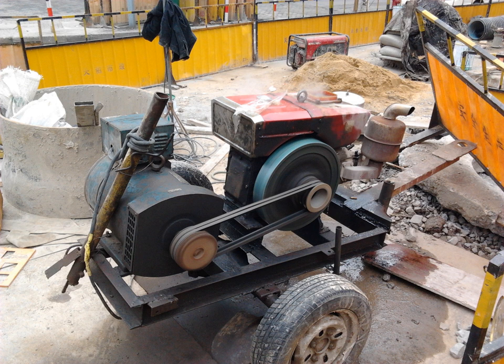This produces power at 50 Hz, which is the frequency used in Europe. In areas where the frequency is 60 Hz, United States, generators rotate at 1,800 revolutions per minute or another divisor of 3,600. Diesel engine generator sets operated at their peak efficiency point can produce between 3 and 4 kWh of electrical energy for each liter of diesel fuel consumed, with lower efficiency at partial loads.